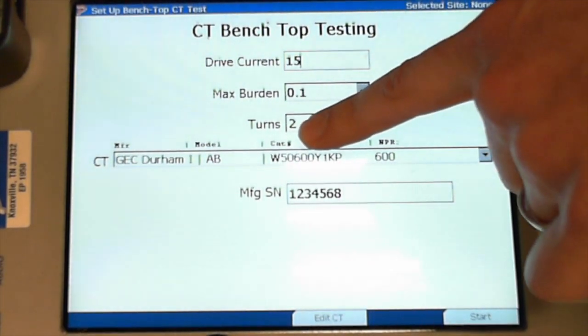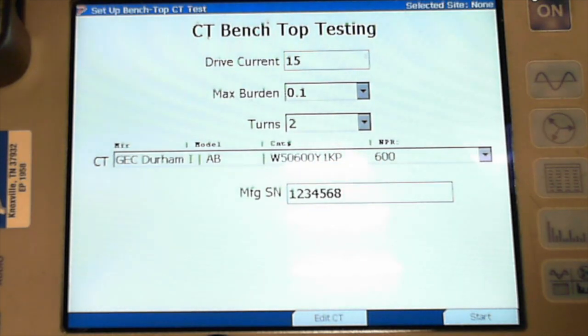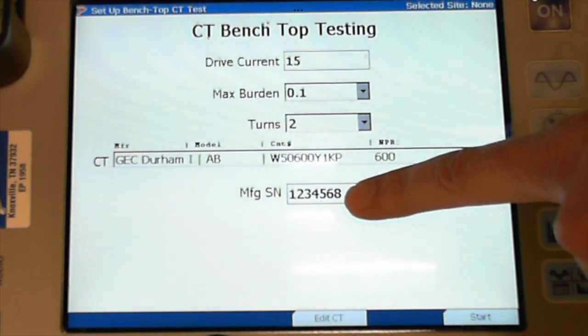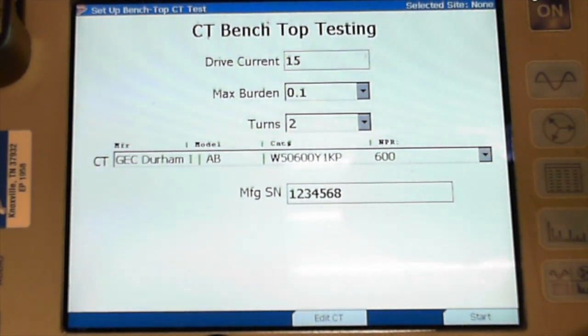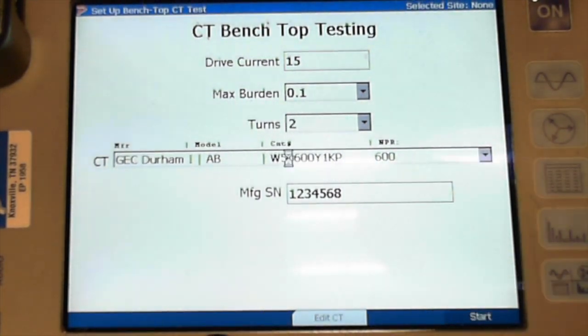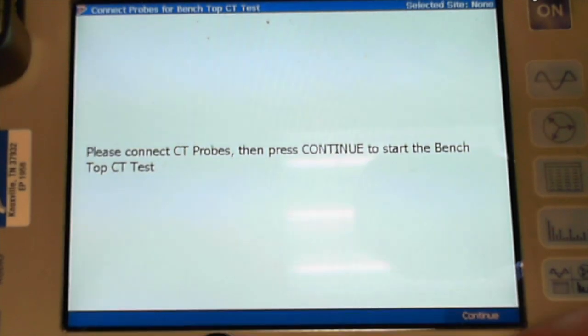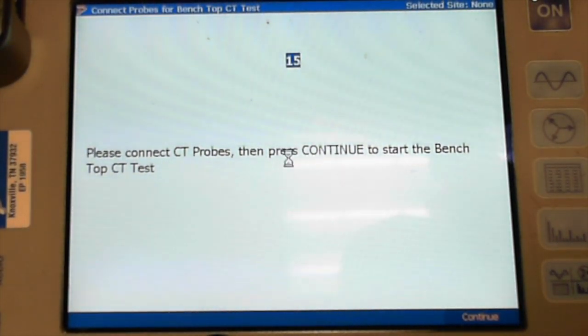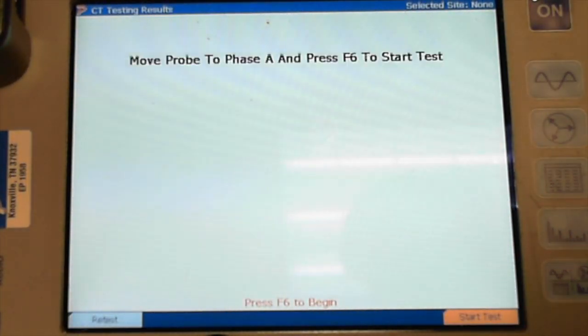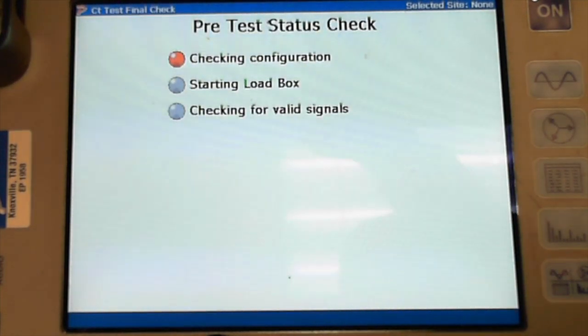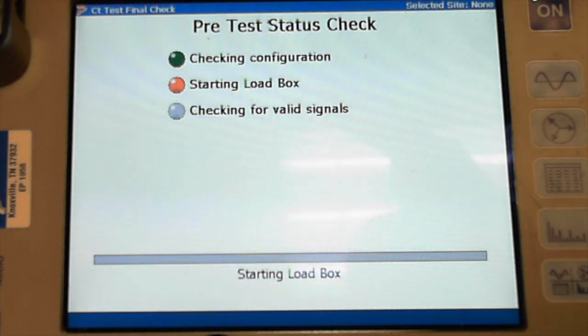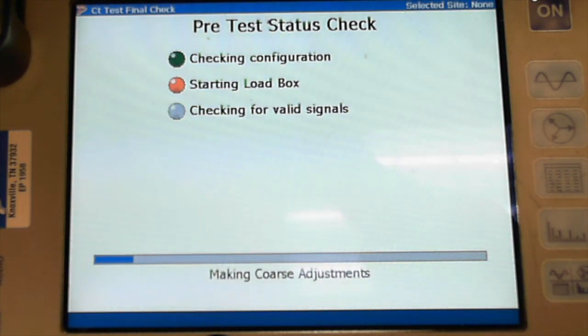So 15 times 2 is 30. So the CT is going to see 30 amps as I drive it. I've got the CT already in my database, and I've already got the manufacturer's serial number. So let's go ahead and start the test. So it goes through the process of actually starting to drive the load. You may hear the fan kick on as it ramps up current.